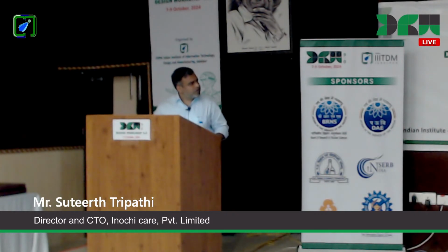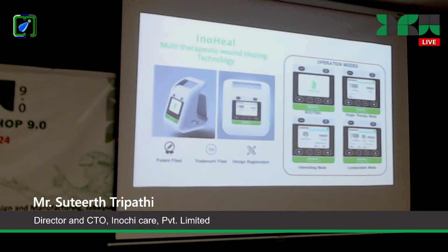Behind the device, if you can see over here, there is a collection canister that is integrated into the device. This collection canister holds all of the exudate that is coming out of the wound. Within this canister, we have an antimicrobial filter so that infection-causing agents cannot enter the device and remain within the canister only. We also have a solidifying agent within the canister so that all of the liquid coming into the canister gets solidified there and does not leak out when the canister is replaced or the dressing for the patient is changed.